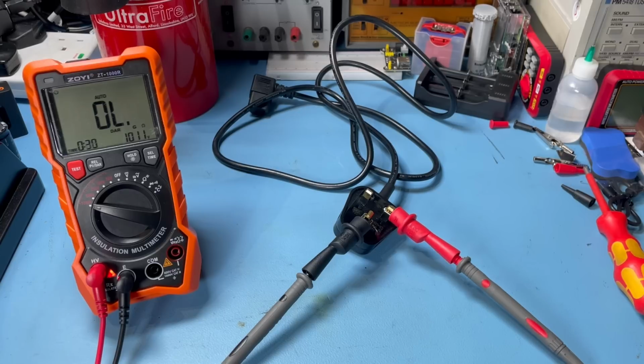Now I'm really interested to know, because this is a much older lead and it passed the insulation test perfectly well at 500 volts and it passed the PAT test. And we can see the DAR has dropped to 0.90. This is not really a problem because you're never going to be putting 1000 volts through that cable. This is just for illustrative purposes, just to show off the meter and what it can do. So it can indeed test at 1000 volts, but you'd really only be using that for really big stuff, big motors, big transformers, three-phase, big armoured cables, that sort of stuff.